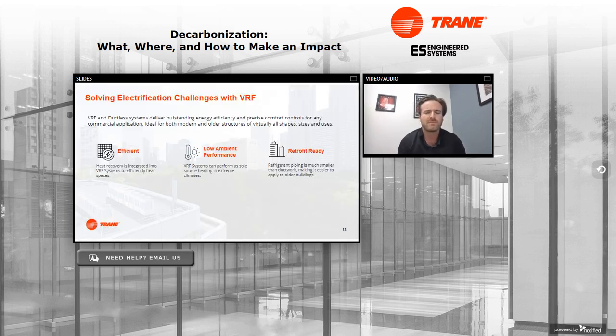VRF can really be useful in three different ways when it comes to solving electrification challenges. We'll go through three of them today. You have efficiency on the left, again that inverter-driven compressor really helps with reducing your total load. Heat recovery is integral too, because the less heat you have to pull from the outside and the less heat you're ejecting to the outside, the more efficient your system's going to be.